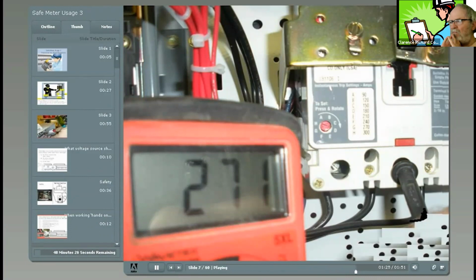When working hands-on with the electrical in this motor control circuit, the verify step means verify the meter works by measuring voltage at a known source, such as the top of a breaker, by measuring from a phase to ground. Verify that no voltage exists from each phase to ground and phase to phase. Verify no control voltage exists in the control circuit. Verify again that the meter works.